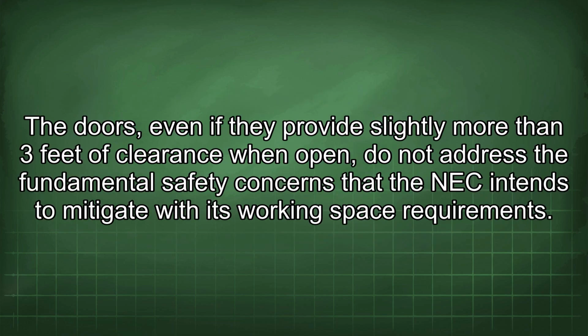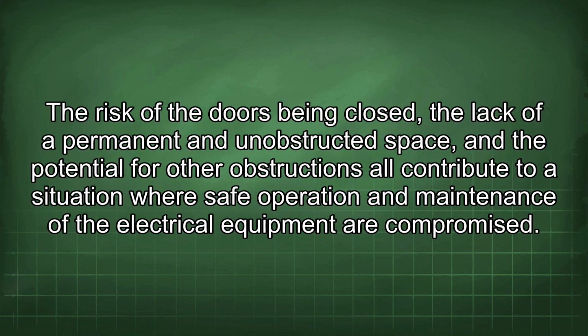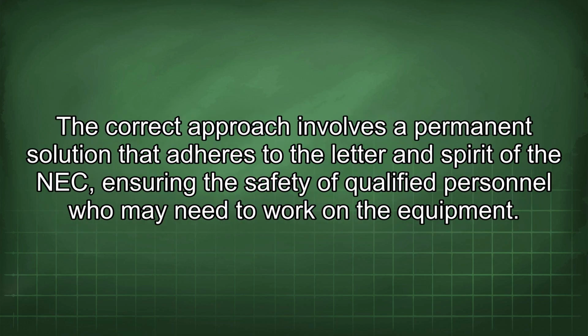The doors, even if they provide slightly more than 3 feet of clearance when open, do not address the fundamental safety concerns that the NEC intends to mitigate with its working space requirements. The risk of the doors being closed, the lack of a permanent and unobstructed space, and the potential for other obstructions all contribute to a situation where safe operation and maintenance of the electrical equipment are compromised. The correct approach involves a permanent solution that adheres to the letter and spirit of the NEC, ensuring the safety of qualified personnel who may need to work on the equipment.